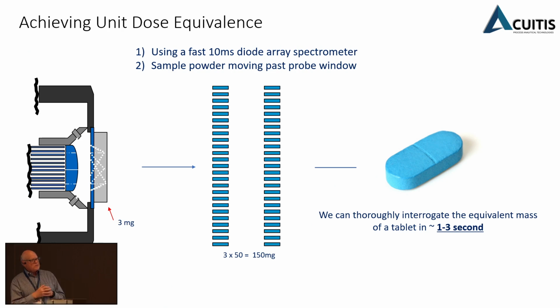So a continuous process is actually allowing us to get round that problem because it is moving the powder, and we can scan repeatedly, integrate a number of scans and get a unit dose weight. In this case, we've taken 50 scans of the moving powder at 3 milligrams each, so our sampling is 150 milligrams, which is getting towards a unit dose weight. Now the question is, for any particular product, how many of these scans do I have to take? If I've got a 500 milligram tablet, how many scans do I have to take to get a representative sample?